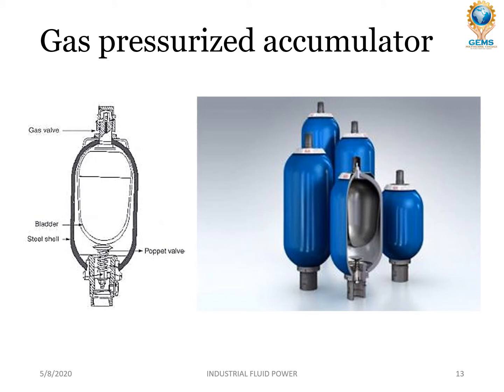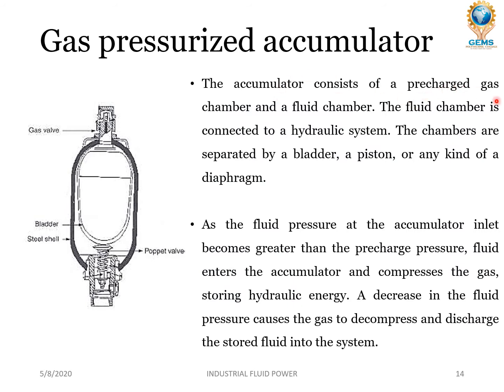Now let's see the gas pressurized accumulator. This accumulator consists of a pre-charged gas chamber and a fluid chamber. The fluid chamber is connected to the hydraulic system. The chambers are separated by a bladder, a piston, or a diaphragm. As the fluid pressure at the accumulator inlet becomes greater than the pre-charged pressure, the fluid enters the accumulator and compresses the gas, storing hydraulic energy.